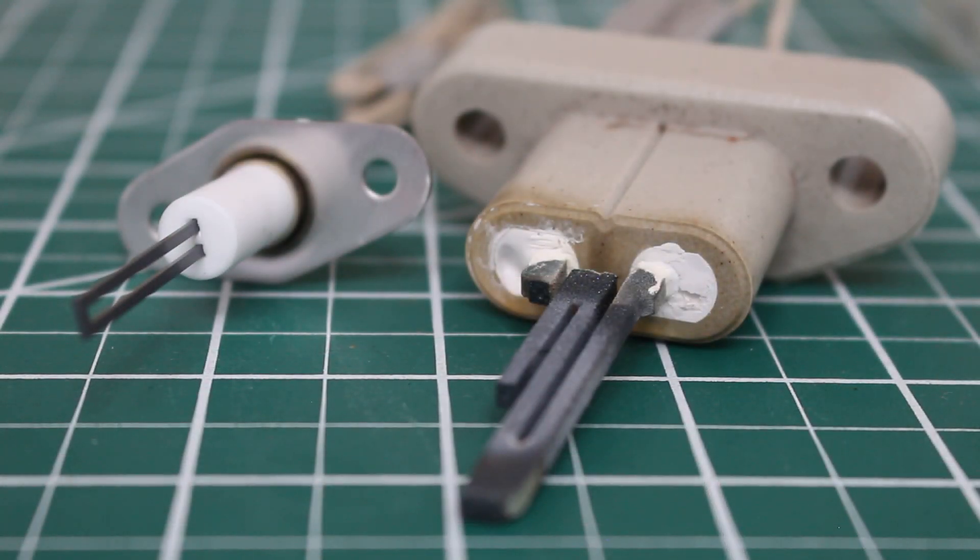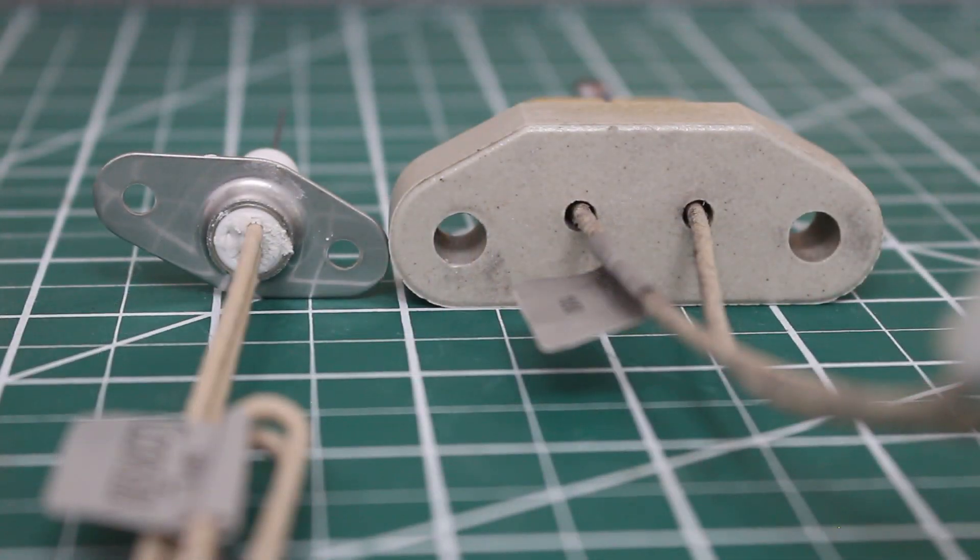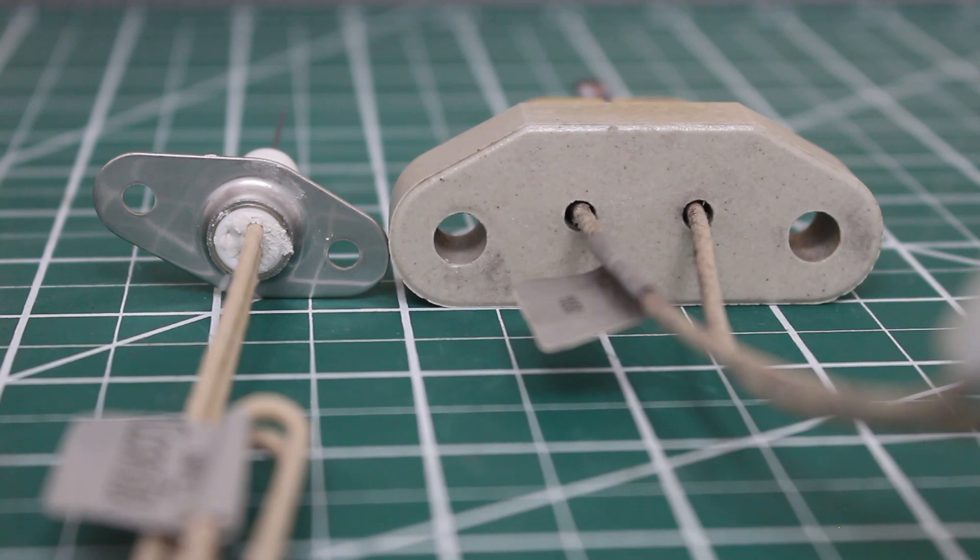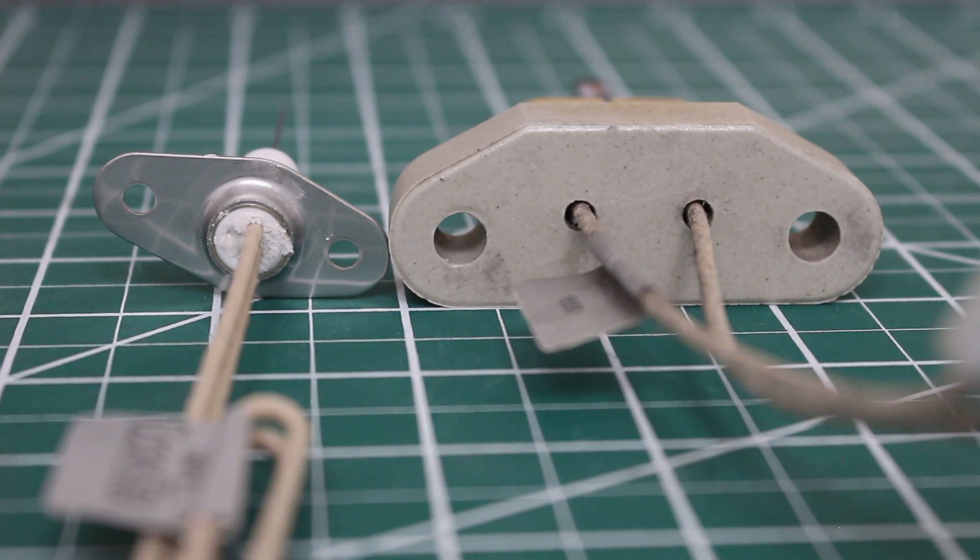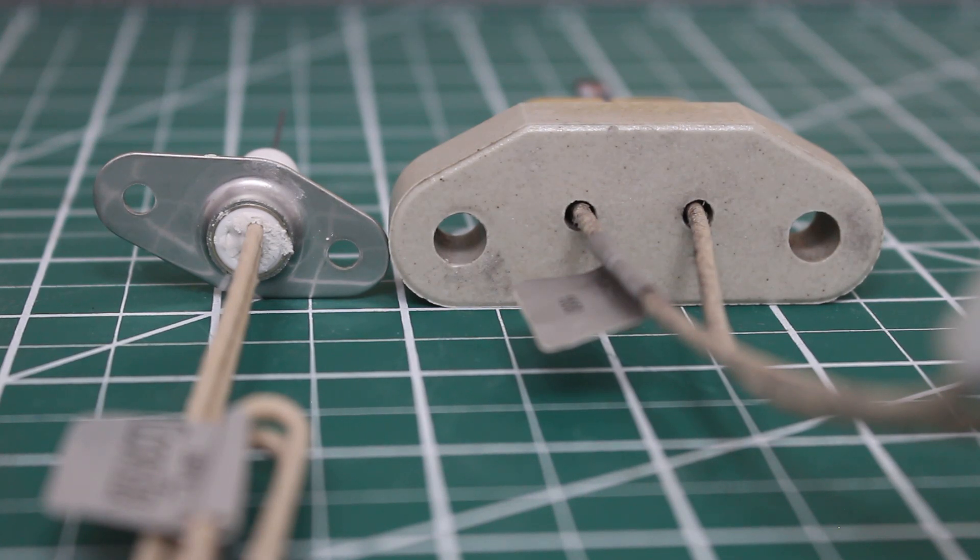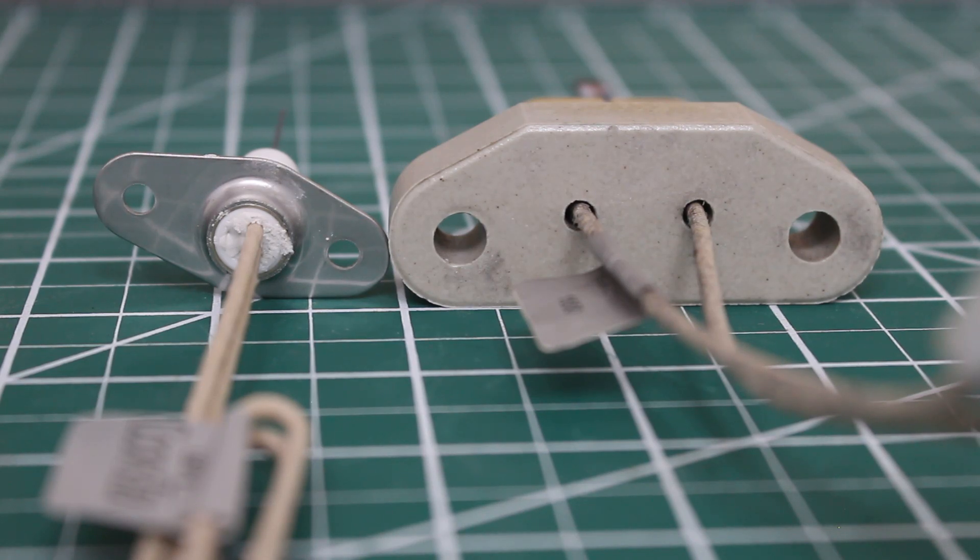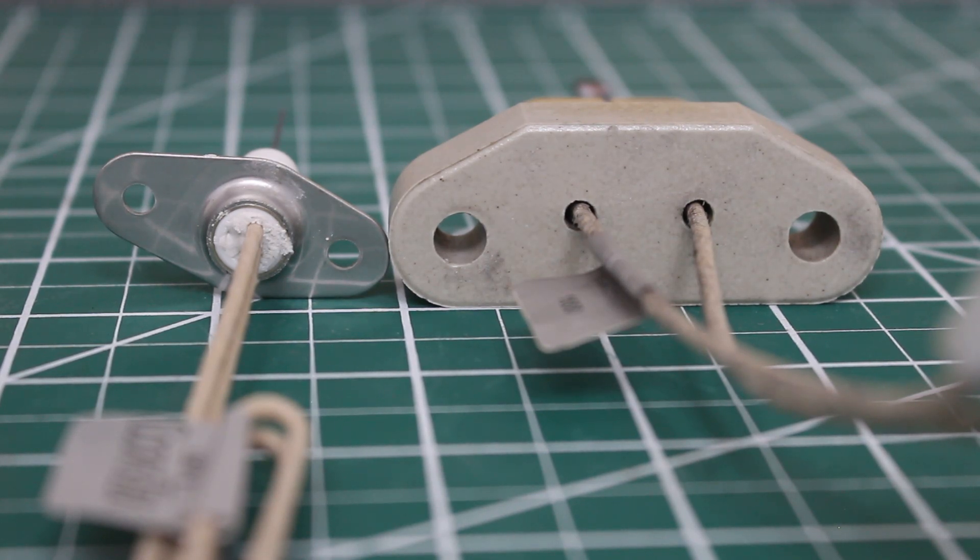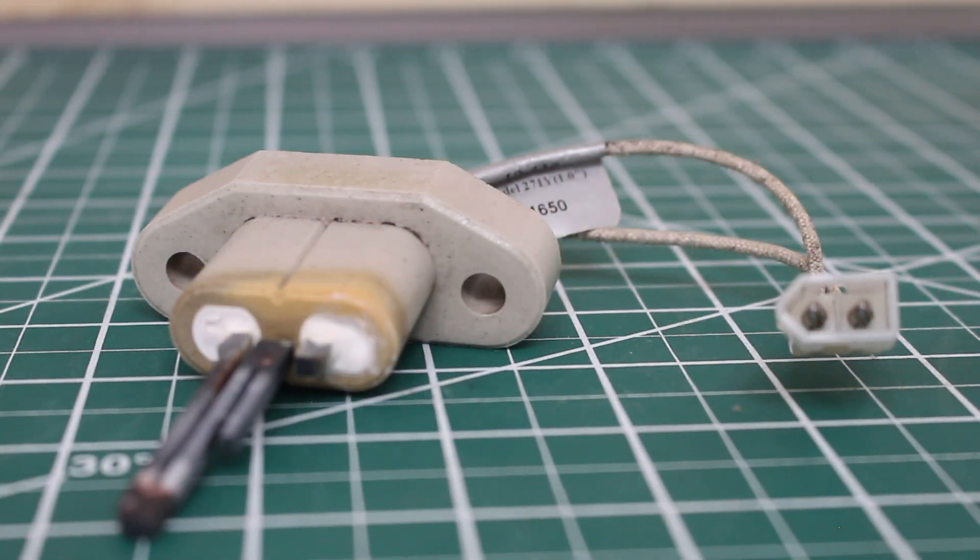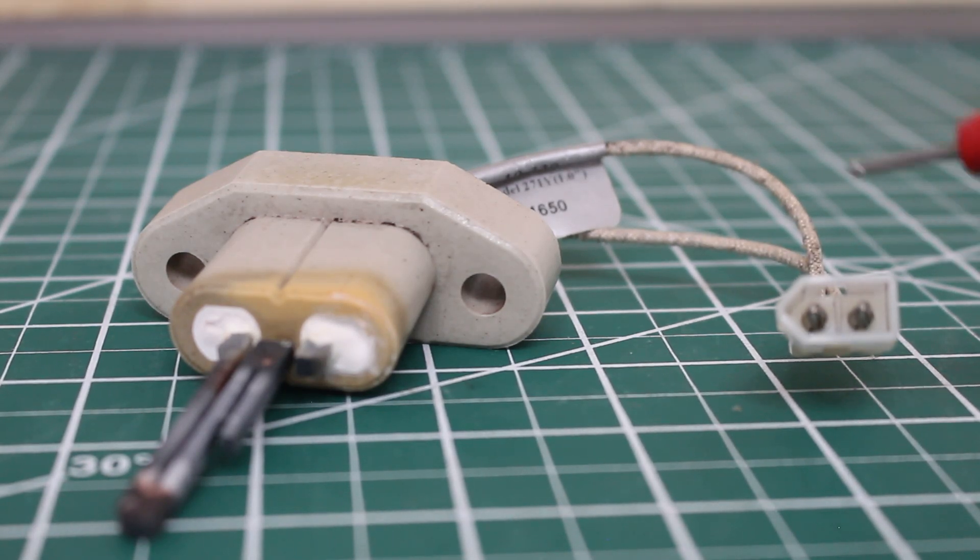Regardless of the type of hot surface igniter you have, in this video you're going to learn two different methods on how to troubleshoot them like a pro. The first method of troubleshooting we will be using today will be using resistance. This is not my preferred method as you will learn later why in this video. But in this case we're going to have the power off to the system and we're going to want to leave the hot surface igniter in the burner section. They are very delicate. Just pulling them out you might damage them.